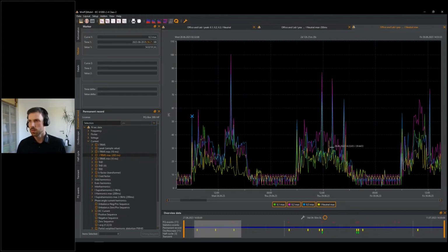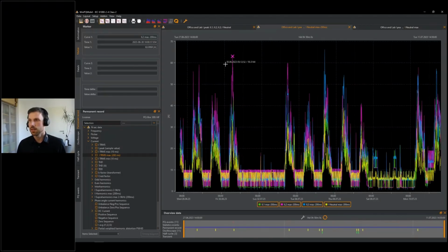565 in the morning. Here it's at around 5:49. So every day at around 6 o'clock, they turn something on, usually the light. And that causes some peaks. I see the 10 millisecond peak in here. And these values are higher than the 200 millisecond peaks. Of course, because I get far more details with the 10 milliseconds.